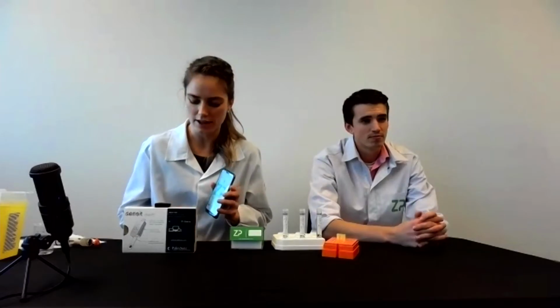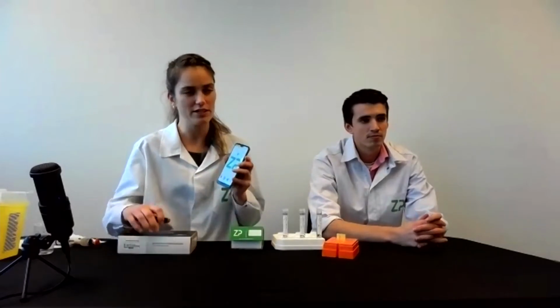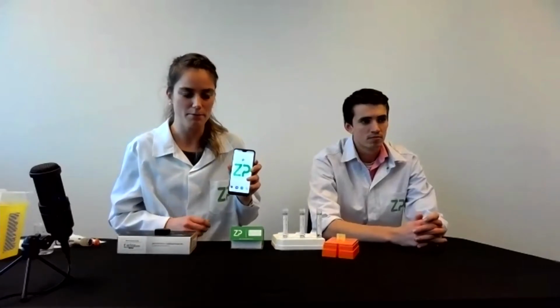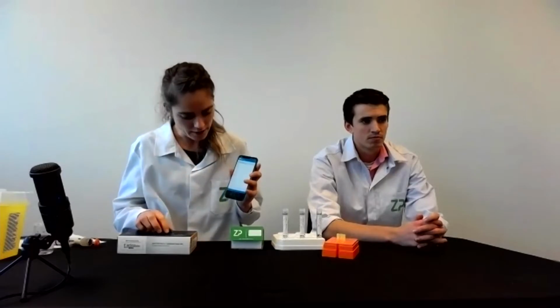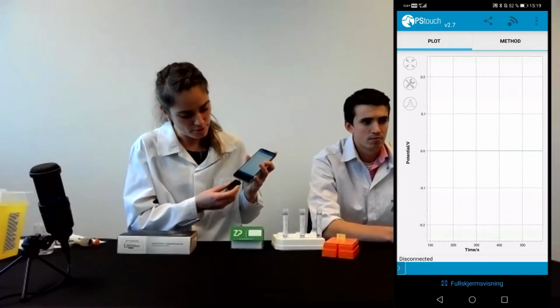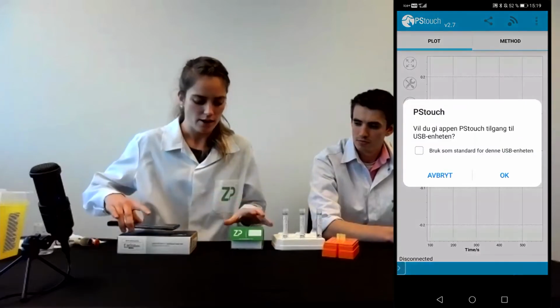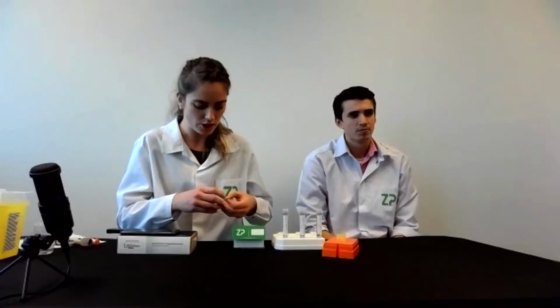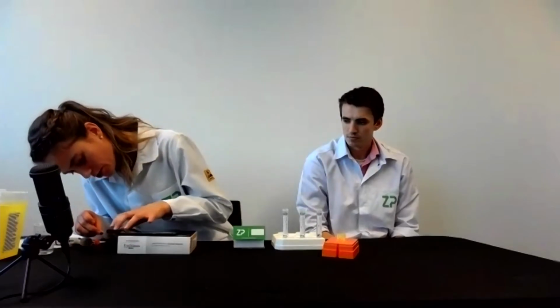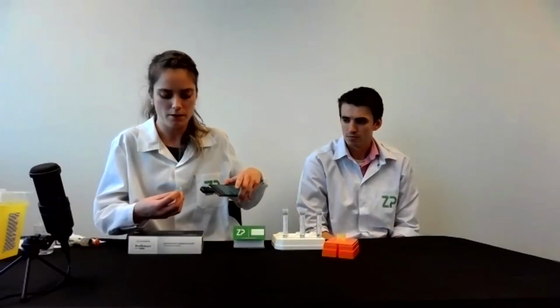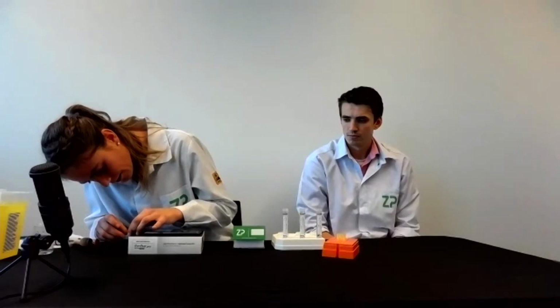All right, so yeah, I'm Solron, and this is Matthew. And as Lutz was saying, this is really simple due to the gear that we have. So what you need is a smartphone with the pre-installed PS Touch app. So we will access that, and we will insert the Sensit Smart, the small potentiostat, into the smartphone. Together with it, we will be using a nitrate sensor from Zimmer and Peacock, which is, as Lutz said, an ion selective membrane. So we will insert that into the potentiostat, and it's important to align the electrodes with the lines of the potentiostat so that the electrodes are connecting.